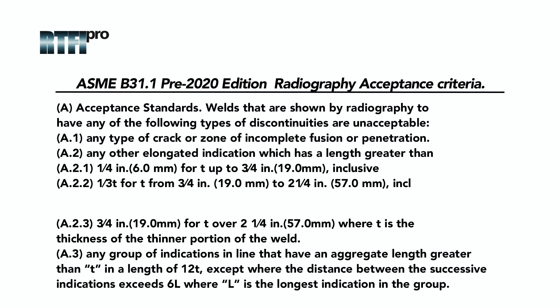A.1: Any type of crack or zone of incomplete fusion or penetration. A.2: Any other elongated indication which has a length greater than — A.2.1: 1/4 inch (6mm) for T up to ¾ inch (19mm) inclusive.